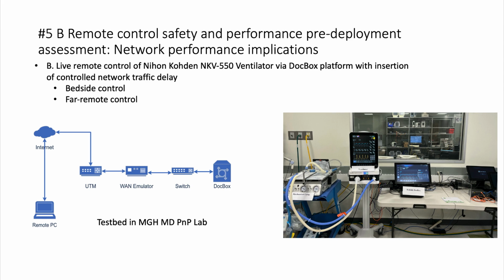So the way this system is set up in this test bed, we will show a DocBox, which you see in the picture on the right, which is connected to the Nihon Kohden ventilator, the NKV550. The ventilator is ventilating a test lung. And with this setup, at any point in this connection, we're able to disrupt the network traffic. We could add delays, jitter, do other things to the network traffic, affect it in only one direction or bidirectionally. So we will do that with this setup that you see here in the slide, and we'll go live now for the demonstration.